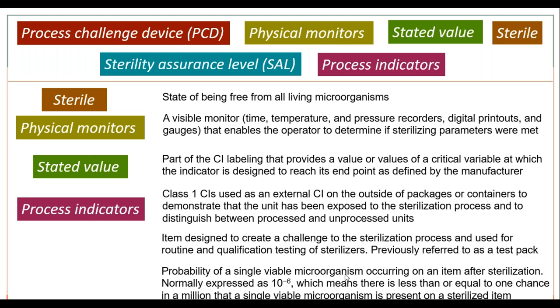An item designed to create a challenge to the sterilization process, used for routine and qualification testing of sterilizers — previously referred to as a test pack — that's our process challenge device. Process challenge devices and biological indicators can often get confused, so that definitely needs to be discussed.